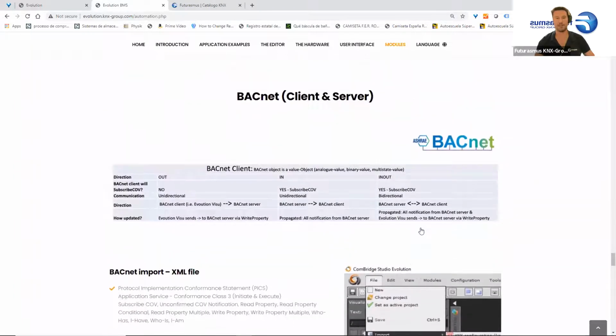The evolution is a BACnet client and server. This means that you can either subscribe to a change of value as a client, where it will read the information from a server, and if the server changes its value, since it's subscribed to the server, the BACnet master will then send the information. Or you can be the other way around, where it will automatically poll the different values to the bus. So all notifications can be propagated via BACnet from the BACnet server.